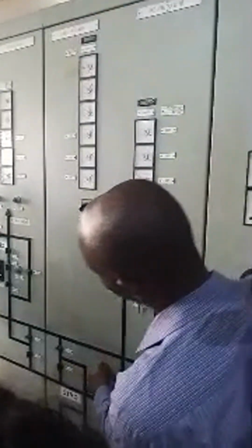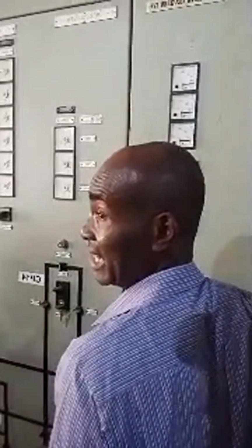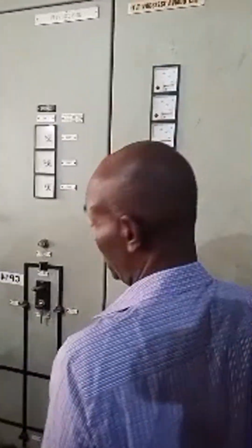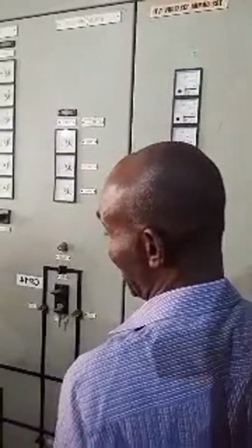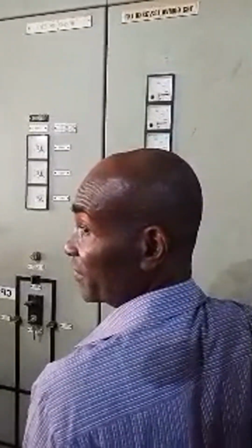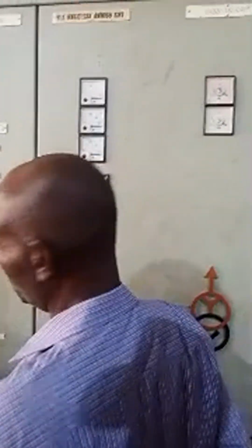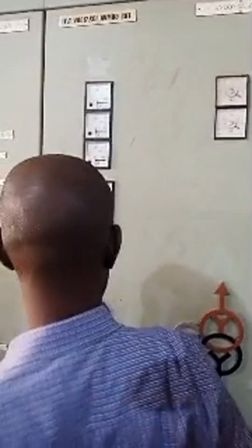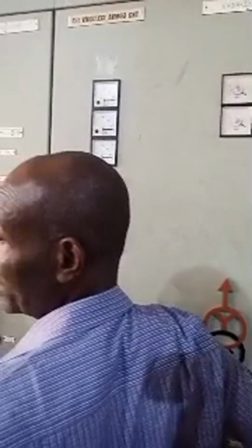Number two is that in case any of this equipment, like this Calago line breaker, has an issue, the PCNM people can come and transfer the protection of that line to this bus coupler CB. Whenever there's a fault on that Insuka line, this one will now trip. But the only thing is that when it trips, it means the two buses will no longer be at the same potential until it is restored, is that okay?